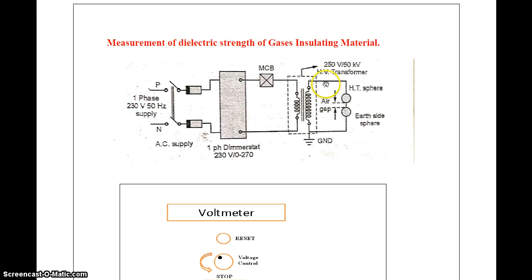Then the secondary side of the high voltage transformer is connected to the two spheres, that is the high tension sphere and another called the earth side sphere, which is connected to the ground. The step up transformer boosts voltage from 250 volt to 50 kilovolt.